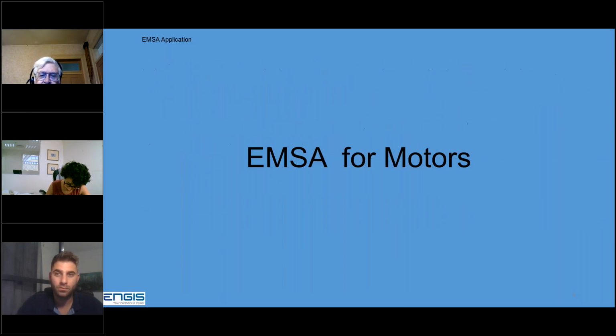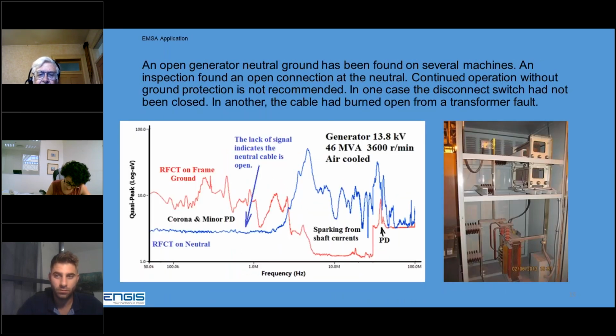The example that I used here on the generator is a very small unit that runs off of sawdust up in Northern California, and they don't want to pull the rotor. They get paid to generate, so their makeup costs are extremely high. So they wanted to postpone working on this generator for a few years, and like the curve shows, there's nothing wrong with that generator. So they put it off, I think, 4 years in their 5-year plan. And the cost of doing an EMSA test on that generator versus pulling the rotor when they didn't need to was, again, about 10 to 1. So any size unit we'll use. The largest ones we've tested so far have been 1100 megawatt nuclear units, and we've tested probably about 6 of those.